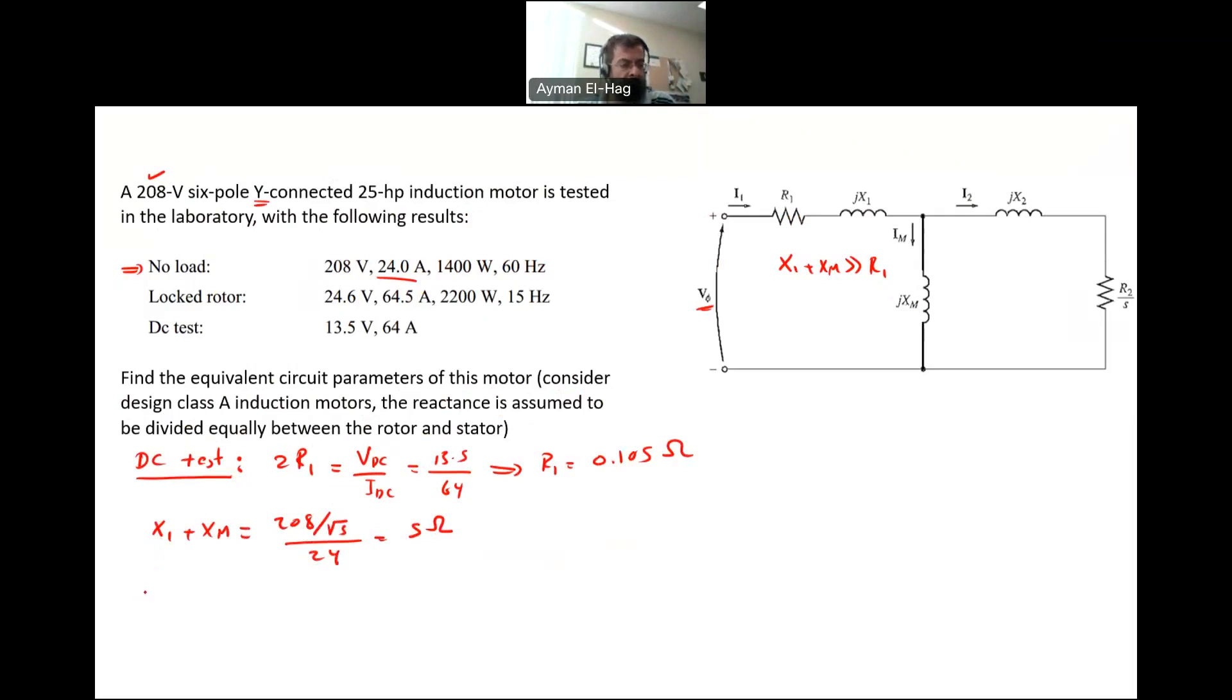Now let's see the locked rotor test. In the locked rotor test, we will find the total Z locked rotor, which equals the voltage 24.6 divided by the current 64.5. This gives me a total impedance of 0.38 ohm. This is the magnitude of R1 plus R2 plus j times X1 plus X2. I need to split the real part from the imaginary part.